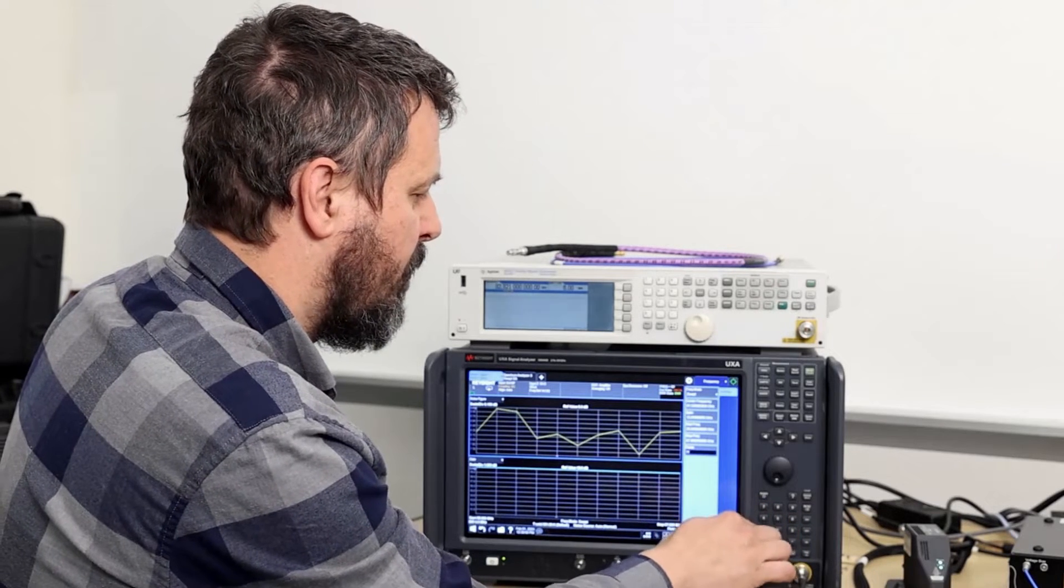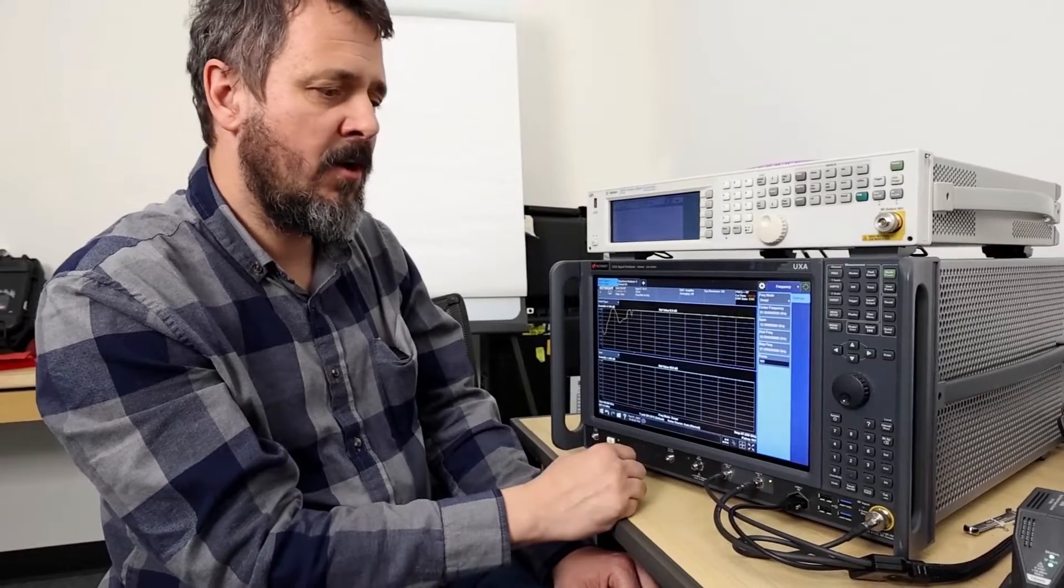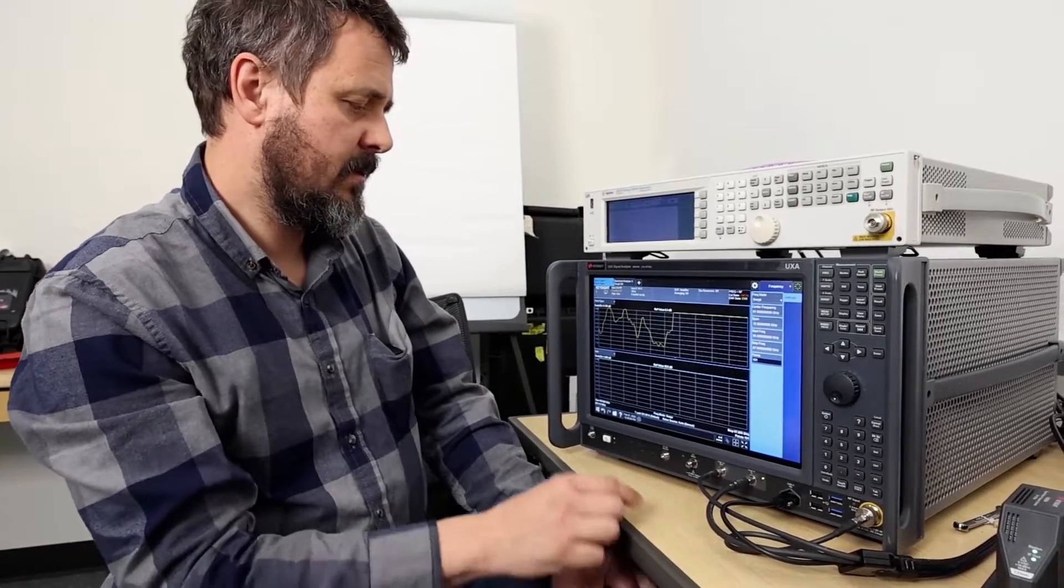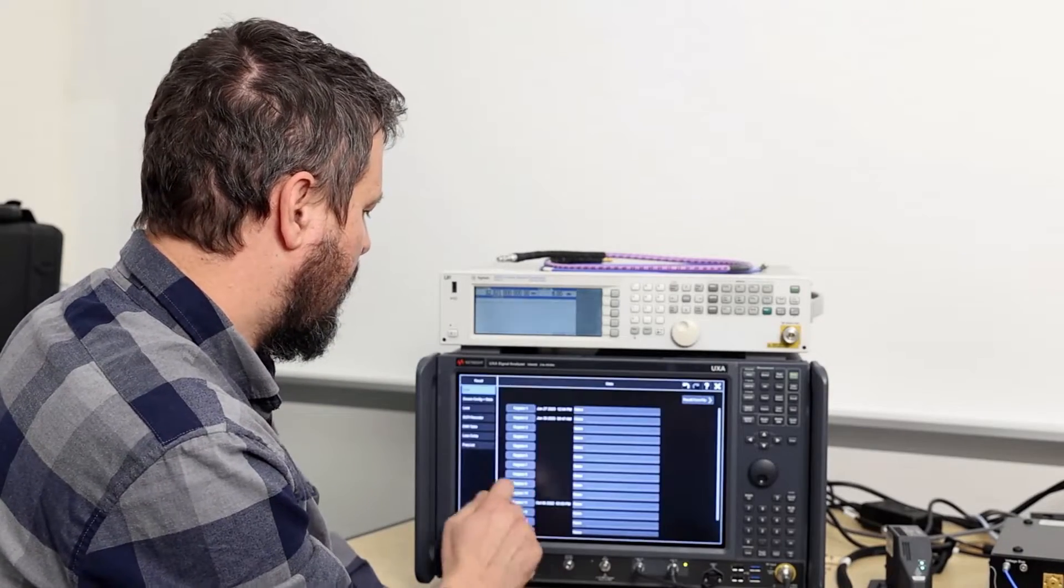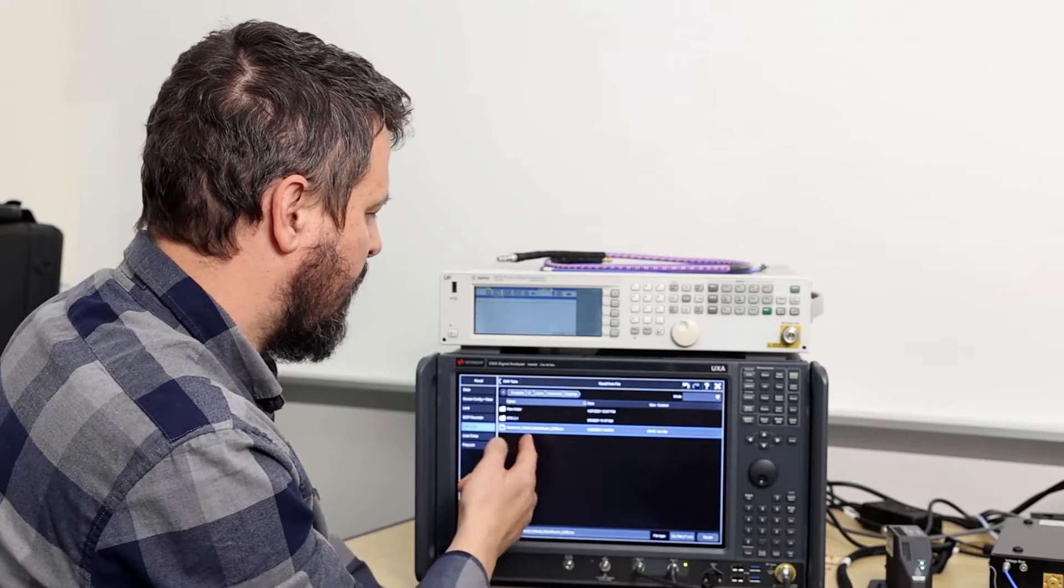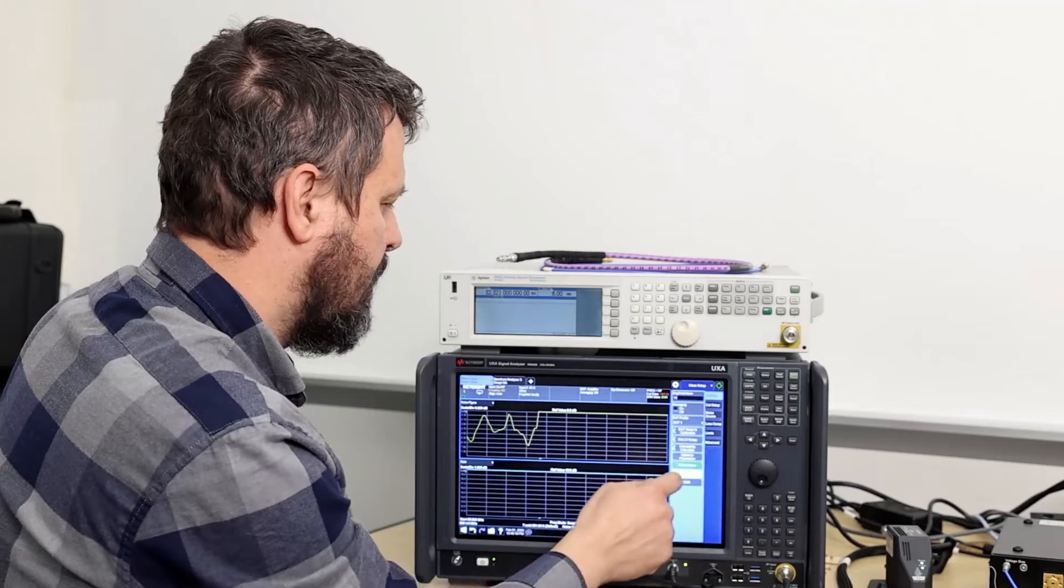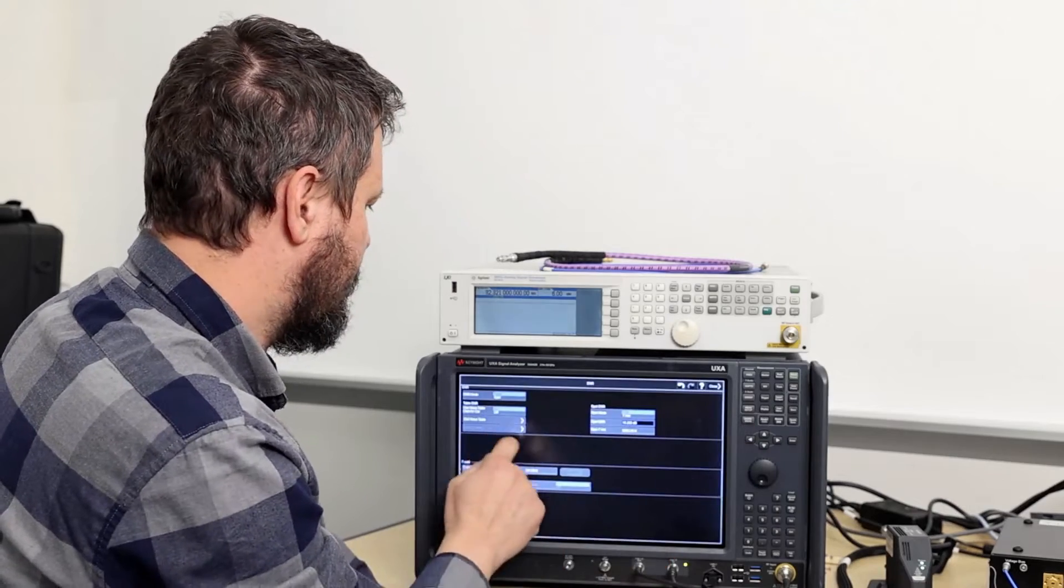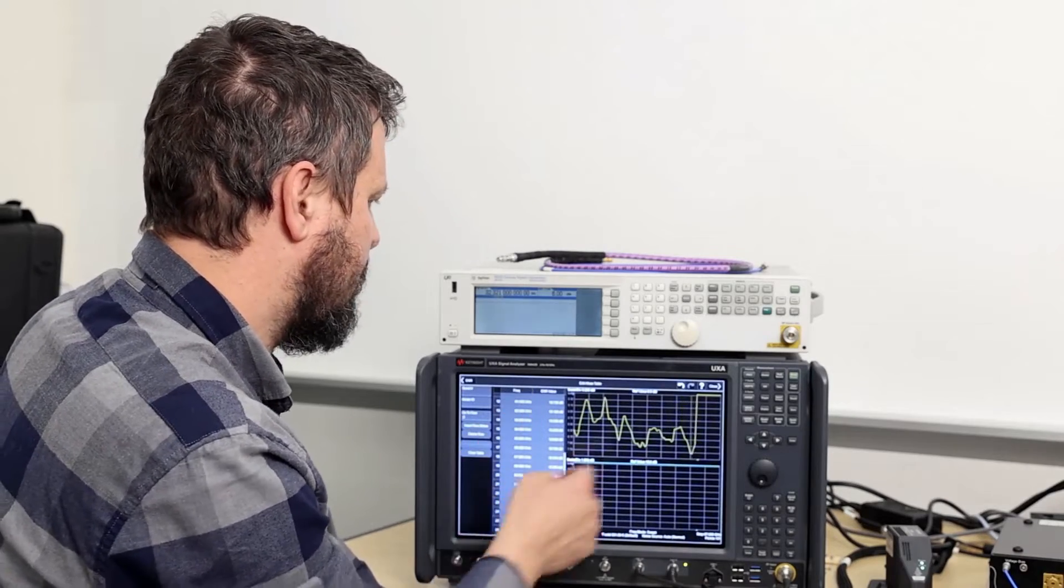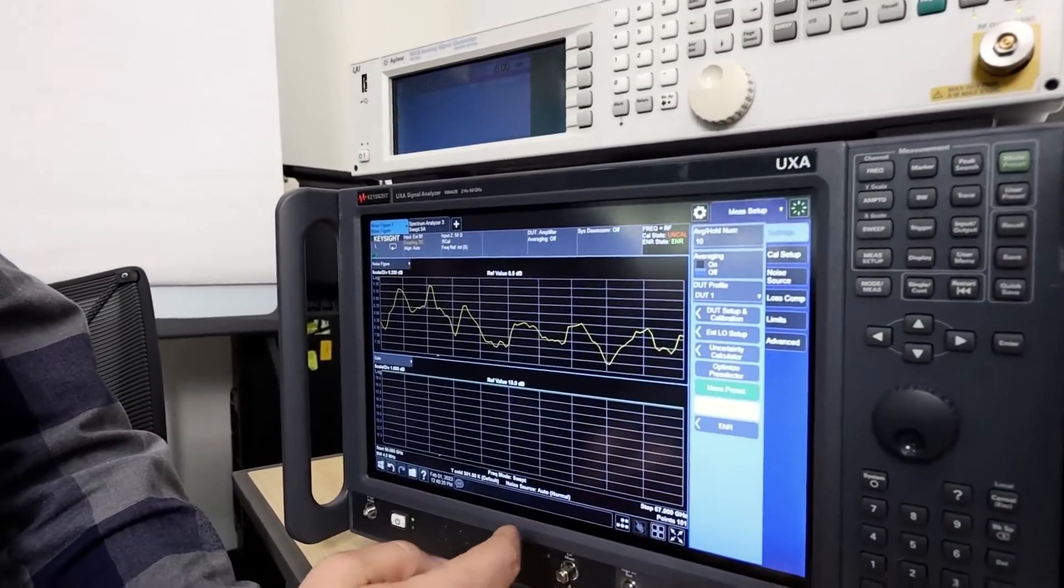I'm going to set 101 points and then I need to load my cal factors for my ENR source. So I'll just go and recall ENR table and I stored it on my desktop. I can look at my ENR values in the ENR table. Here's all my ENR values. So that looks good. It's not giving me any warning messages.